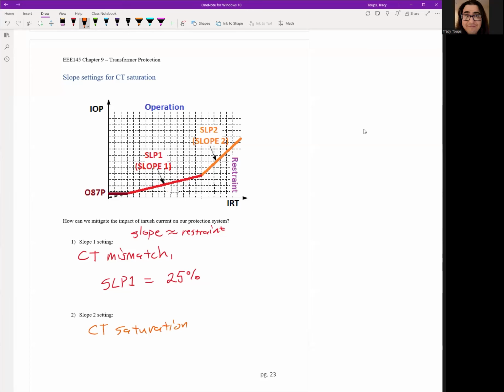And the reason why is CT saturation only happens whenever we have high fault current levels. Okay, this x-axis is amps. And so on the lower side, before super high fault current, CT mismatch is an ongoing thing. Even at low current levels, you still have CT mismatch. So slope 1 takes care of that. But once you get to the fault current level, when one CT saturates, we might get past that 25% slope 1 setting, which we don't want to operate because this can be an external fault current. Again, if it's an external fault, we don't want the 87 relay to operate. So we need to make sure we have a stronger slope to stop the 87 from tripping. So here we're going to have a slope 2. This is usually 60% or so.